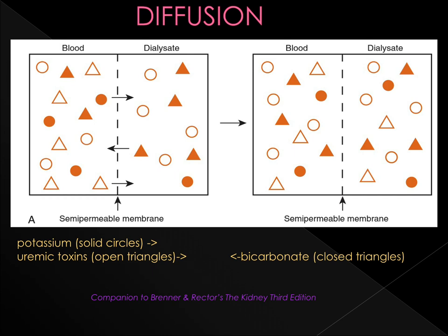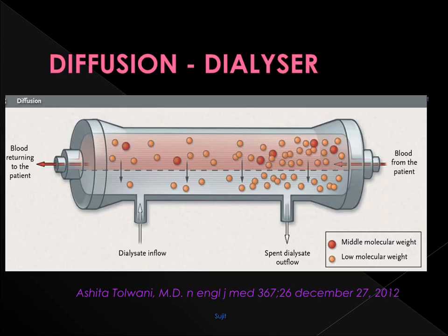Solutes with higher concentration in the blood compartment — such as potassium shown in solid circles and uremic toxins shown in open triangles — diffuse through the membrane into the dialysate compartment. Conversely, solutes with higher concentration in the dialysate — such as bicarbonate represented by closed triangles — diffuse into the blood compartment. Solutes such as sodium and chloride with nearly equivalent concentrations in both compartments move little across the membrane. Solutes move from the side of higher concentration to the side of lower concentration, from blood to the dialysate. Diffusion is best for clearing low molecular weight substances such as urea and creatinine.